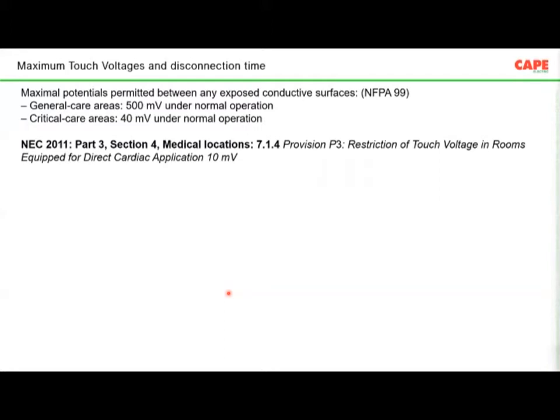Now, in order to reduce the accidents or the amount of the problem, different standards recommend different requirements. For example, NFPA 99, which is followed in America, says that in general areas under normal condition, more than 500 millivolt shall not be allowed, and in critical areas, 40 millivolt in normal condition shall not be allowed. That means all the exposed and extraneous conductive parts must be interconnected in such a way that more than this voltage is not experienced between two metallic parts.